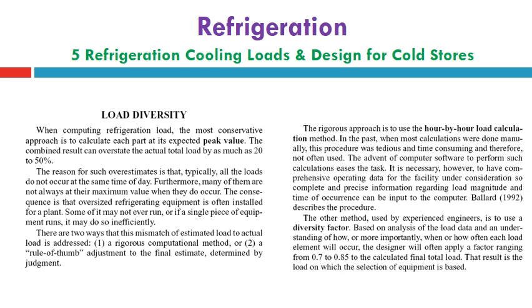The first is to use an hour by hour load calculation method similar to the HAP, which is named Hourly Analysis Program, which can be used for air conditioning systems to take into account each load component by hour and take the total summation, and estimate the maximum expected load during the day and take the total load based on this maximum or worst case scenario which can happen during operation. In the past, when most calculations were done manually, this procedure was tedious and time consuming and therefore not often used.